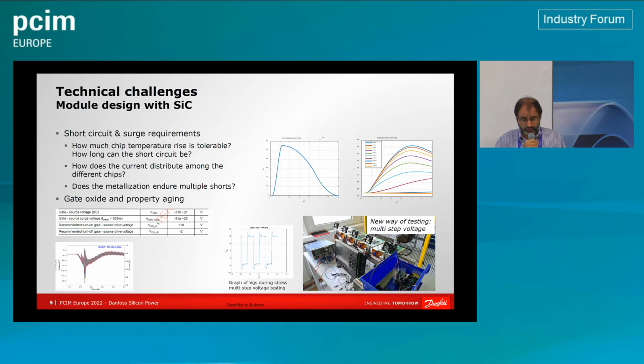One of them is short circuit and surge requirements. On the left-hand side you see a pulse during a short circuit—a short period of time—and the temperature rise at each layer in the vertical stack of the module. The top layers, closest to the junction, reach much higher temperatures, around 800 or 900 degrees, while the lower layers deep inside the substrate are less affected.